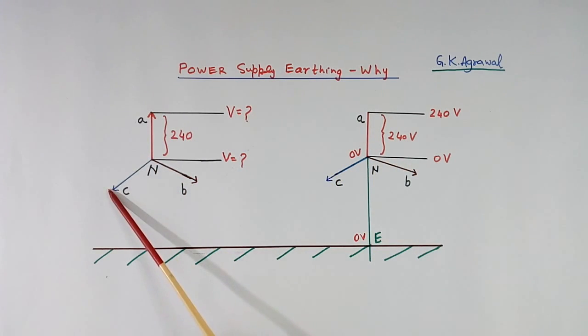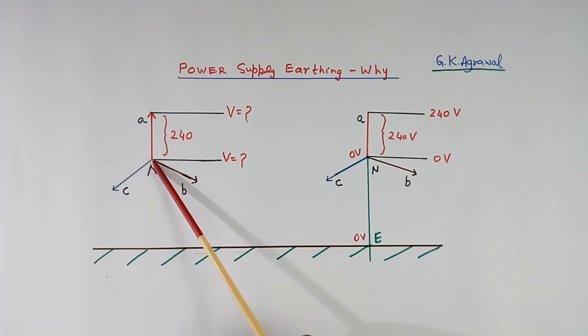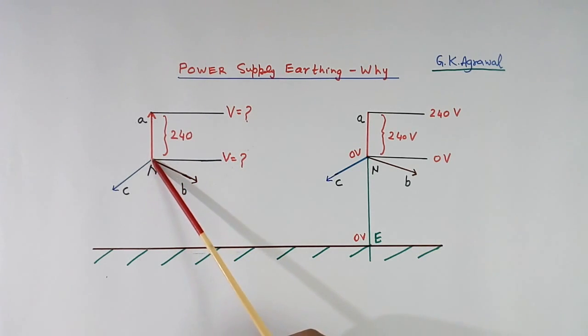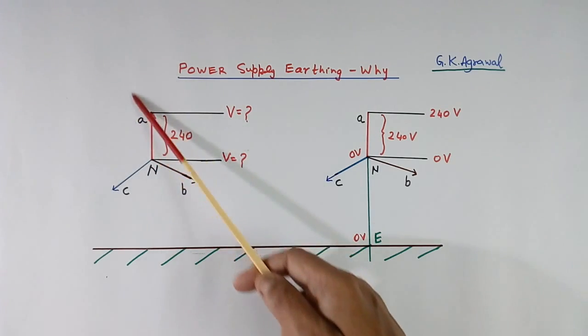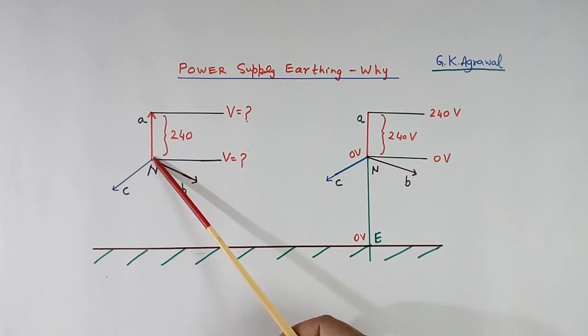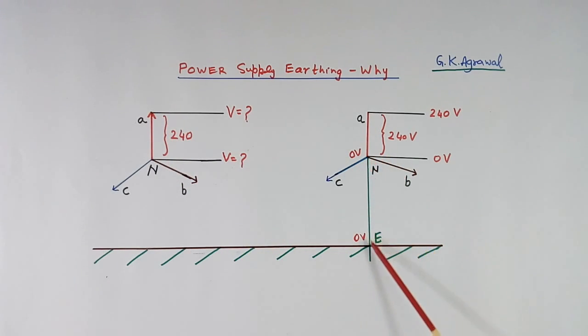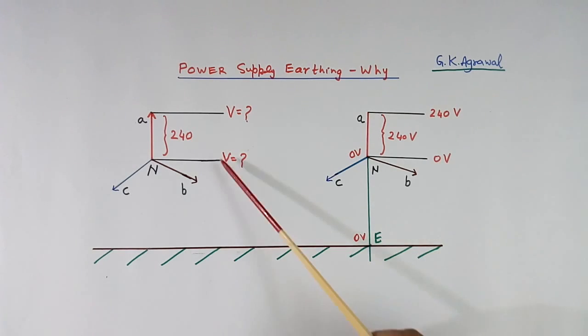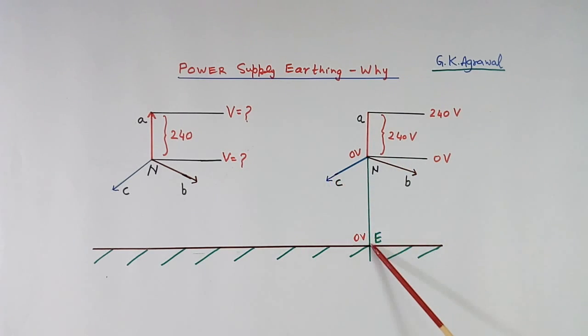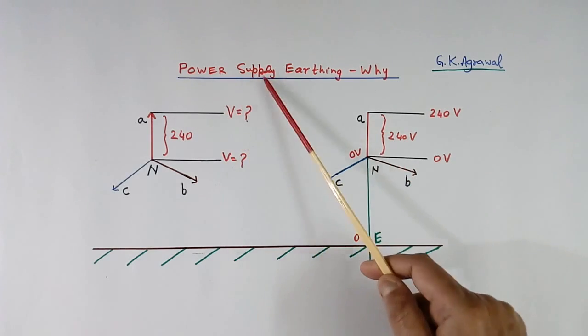Here I have shown the secondary of the transformer. This phase voltage is 240 volt. If this neutral is not connected to earth, we know the voltage across this, but we don't know the voltage of this point with respect to earth — it is called a floating system. Suppose some lightning or switching impulse comes; this point may go to very high voltage, so this equipment may fail because the voltage of each point with respect to earth is not known. But here, where neutral is connected to earth, this point becomes 0 volt. The voltage of each point is fixed and known with respect to earth, so this is a safe system. Here equipment will fail; here equipment will not fail. So power supply side earthing is done to protect the equipment.